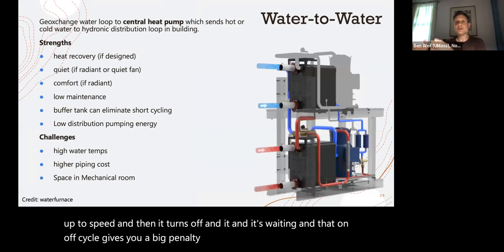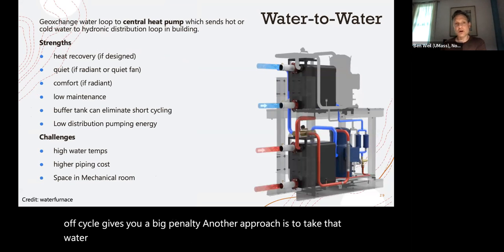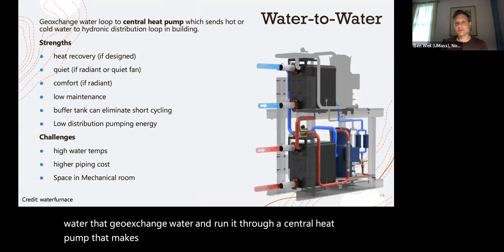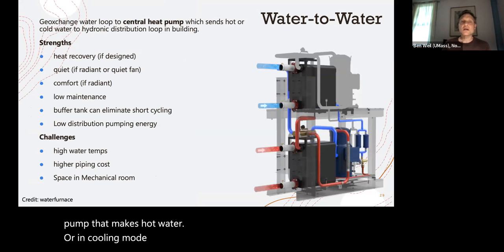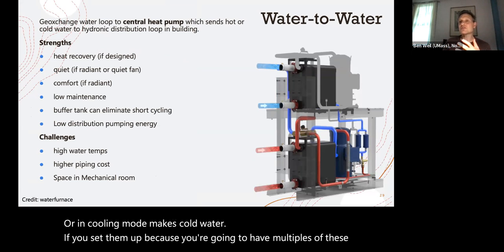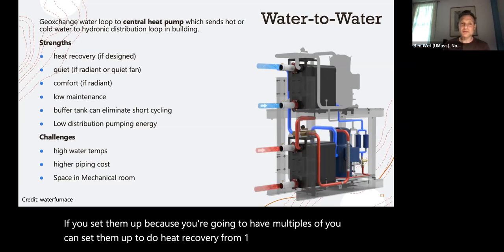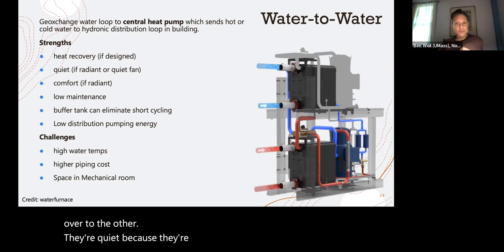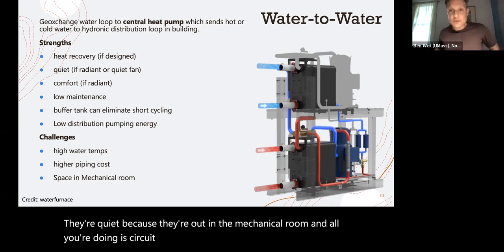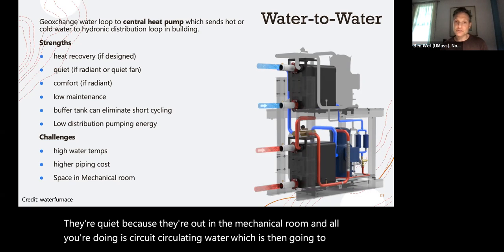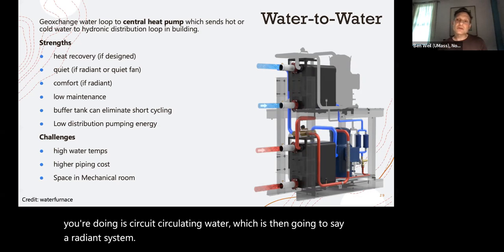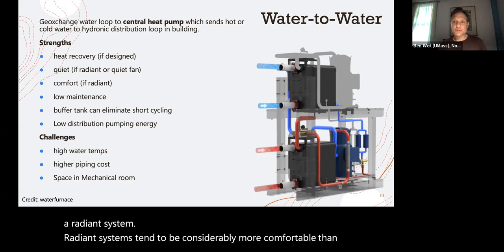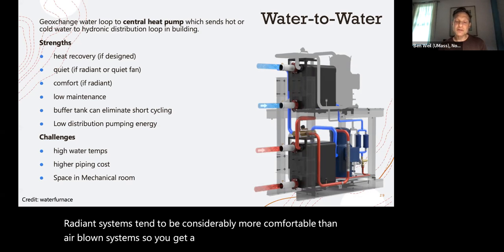Another approach is to take that water, that geo-exchange water, and run it through a central heat pump that makes hot water, or in cooling mode makes cold water. Because you're going to have multiples of these, you can set them up to do heat recovery from one heat pump directly over to the other. They're quiet because they're out in the mechanical room, and all you're doing is circulating water, which is then going to, say, a radiant system. Radiant systems tend to be considerably more comfortable than air blown systems, so you get a comfort benefit.